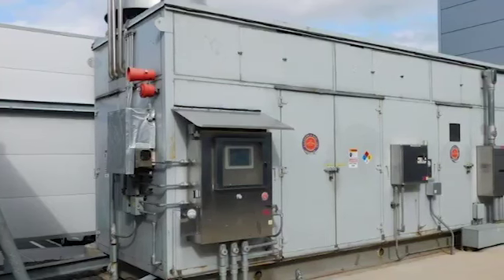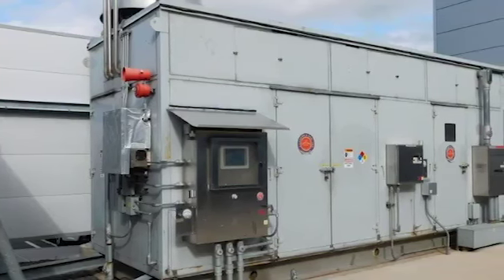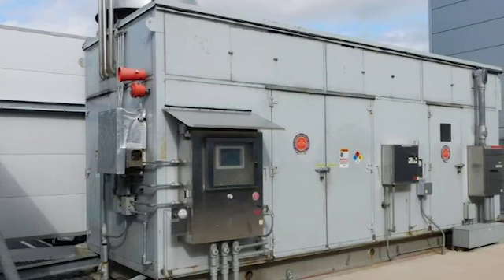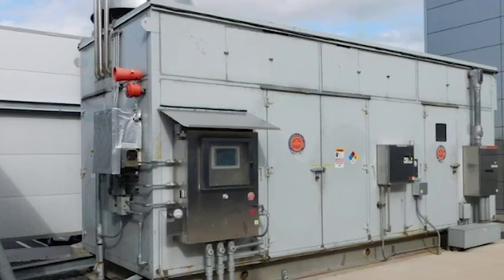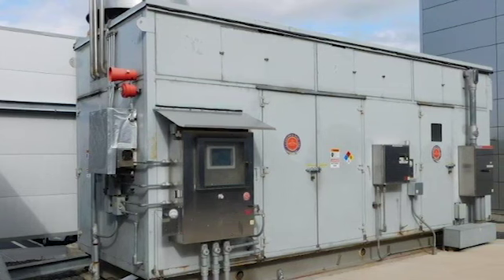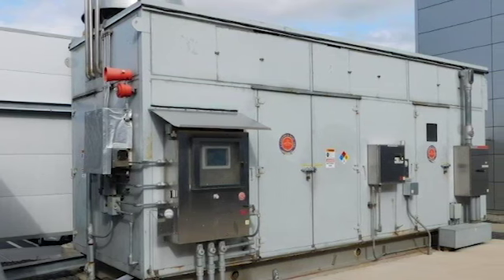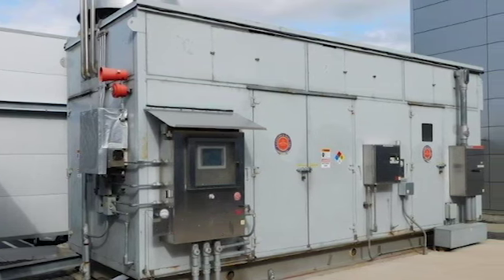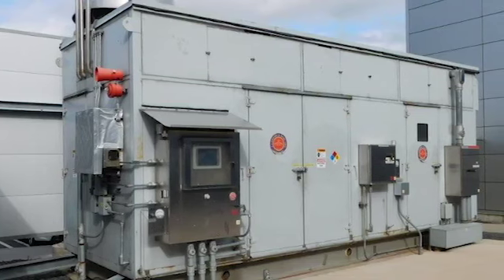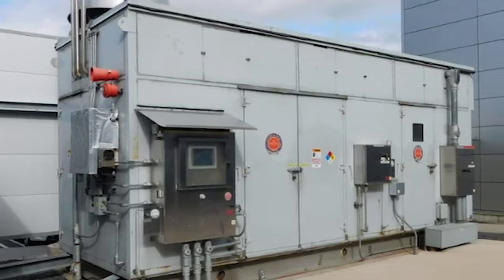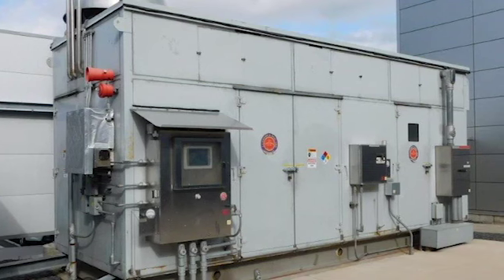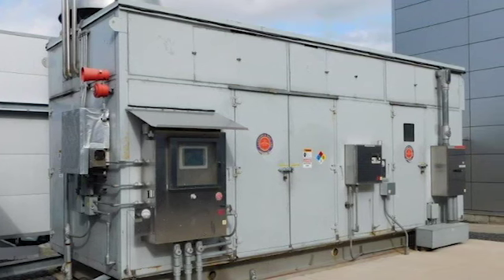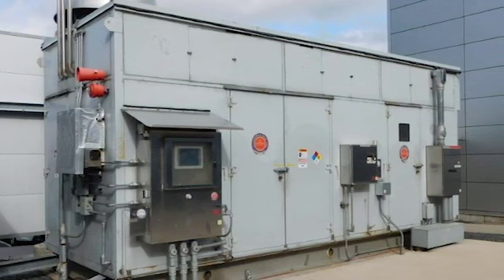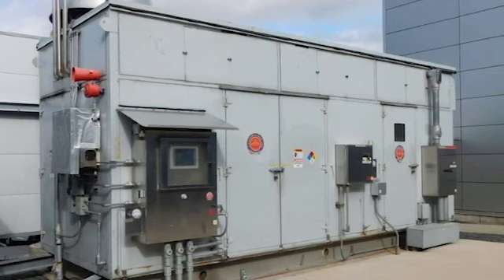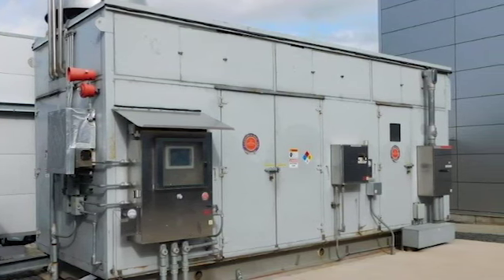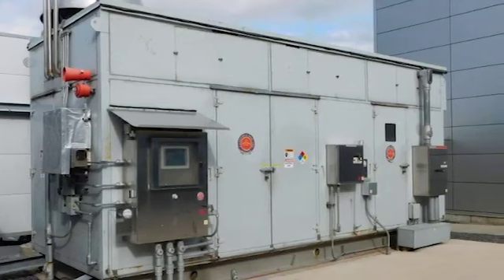Take a quick peek at the gas compressor. The gas compressor is necessary because the street pressure of the gas only takes us to about 50 psi, and we need about 150 psi at the injector. So we need this gas compressor to bring up the gas pressure and to normally run the turbine. It does have a variable speed drive on it, so it does match its energy use quite well, and becomes part of our cogen train.